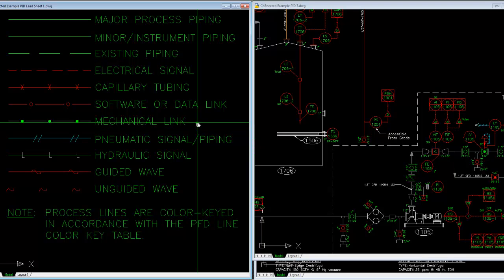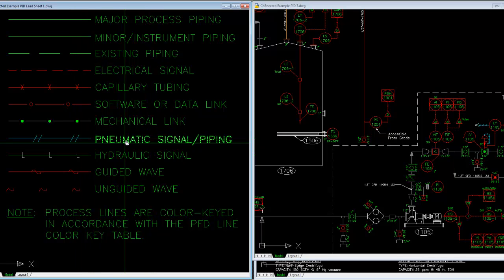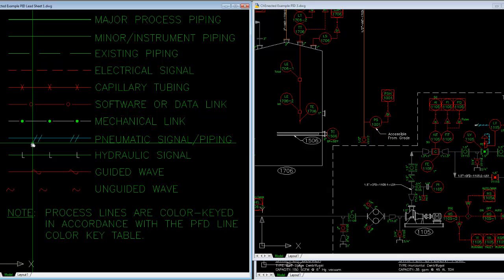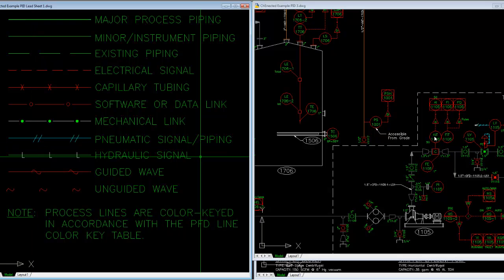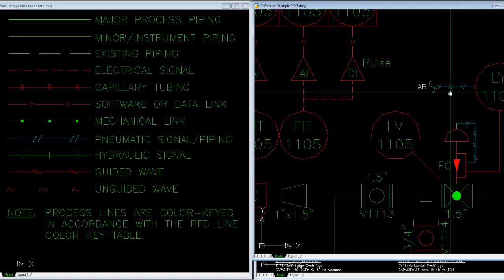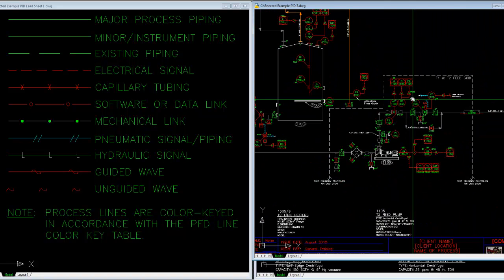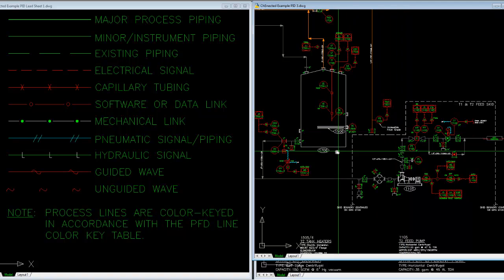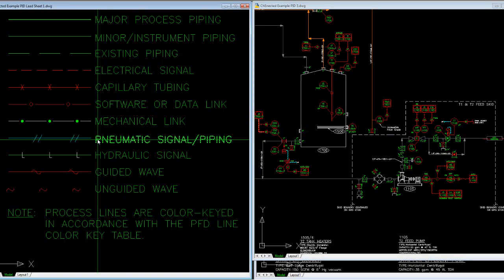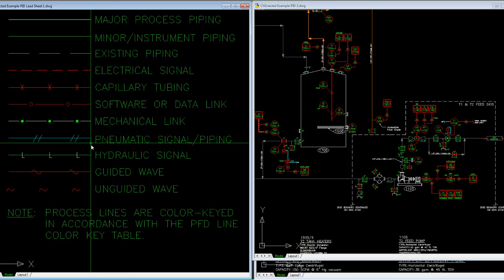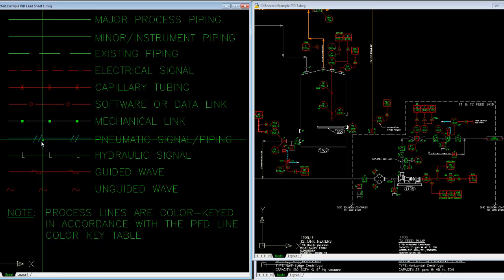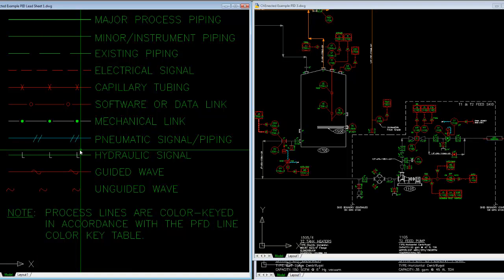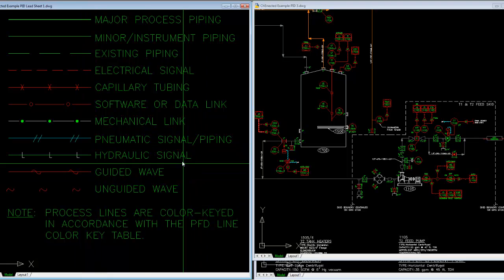The use of pneumatic signaling or piping with the double lines on an inclined basis is very common in instrument air systems. I use those a lot on valves and instrument air symbols, not to be confused with the actual distribution of air throughout a plant where I tend to use the actual just solid line. When it becomes used in a manner of running instrumentation, then I switch over to this, and again, it's a discretionary thing. The point is that you're making an indication that that air symbol is driving instrumentation.